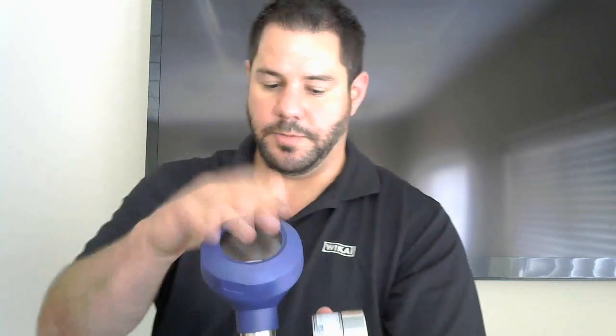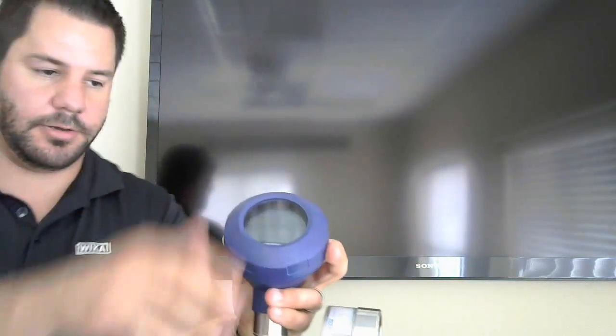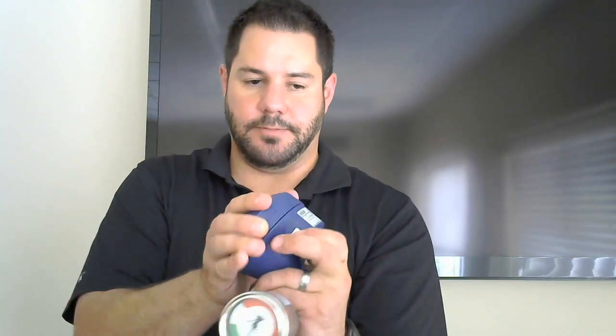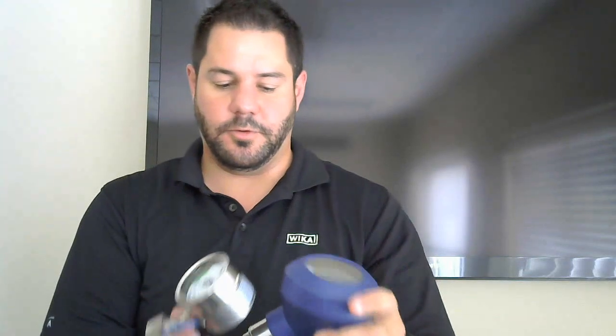Then we go to this one again, which we call our UPT-20. Now, we're not talking about the diaphragm monitoring system on this, we're just talking about the portion up here. This has the ability to have HART, field bus, any of those installed into it. So this will go up against your higher end transmitters in the industry. You'll see some higher end transmitters when it comes to food and beverage, but mostly you're going to see those in pharmaceutical and that style industry, pharmaceutical life sciences.